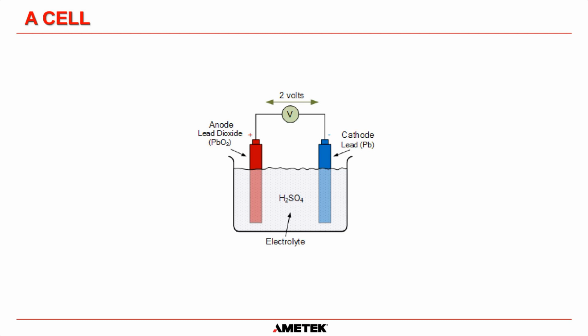What happens when you put a load on the lead acid cell is the sulfuric acid, the electrolyte, starts to get absorbed into the negative plate, the cathode, and it gets turned into lead sulfate. A lot of people say, obviously there's no such thing as perpetual energy, so as the battery discharges, where does the energy go? The energy basically gets taken out of the electrolyte. The acid gets taken out of the electrolyte and absorbed into the negative plate as lead sulfate. That lead sulfate starts to create a barrier on the surface of the negative plate, which makes it harder for the lead to take more acid out of the electrolyte.